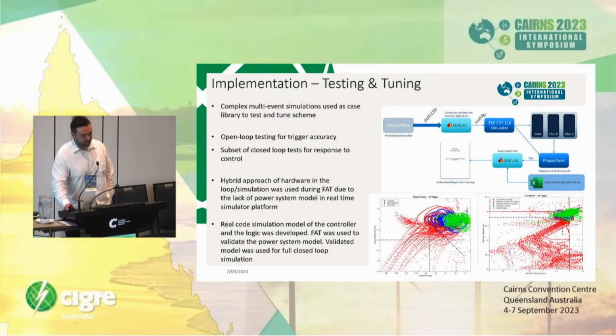So a little bit about the implementation, testing and tuning of the scheme. There were a number of case libraries that were prepared to simulate complex multi-event simulations and to help with validating and tuning the scheme. Open loop testing was conducted mainly for determining trigger accuracy and validating the hardware. That was at ElectraNet's engineering evaluation facility, where they have an RTDS simulator, and that would play back the data and validate the scheme. And there was also a subset of closed loop tests for response to the control action that was taken.